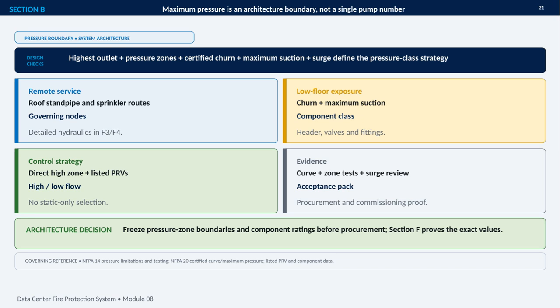At the low floor, churn pressure combined with maximum suction determines the required component class for headers, valves, and fittings. The control strategy must also work across both high and low flow conditions. That may mean a direct high zone with listed pressure-reducing valves, but it cannot be based on static pressure alone. The evidence must include the pump curve, zone tests, surge review, and a complete acceptance package that supports procurement and commissioning. The architecture decision is to freeze pressure zone boundaries and component ratings before procurement.